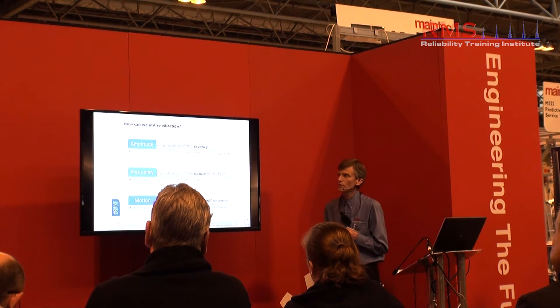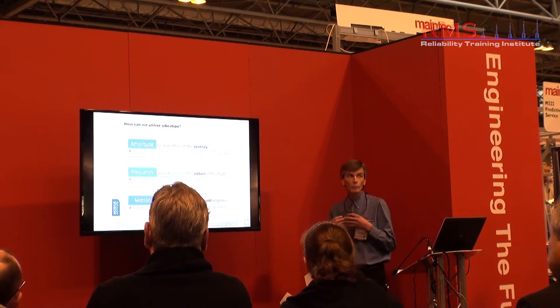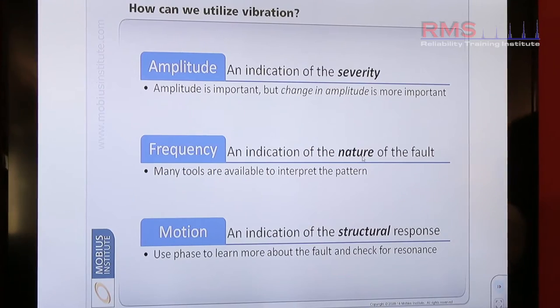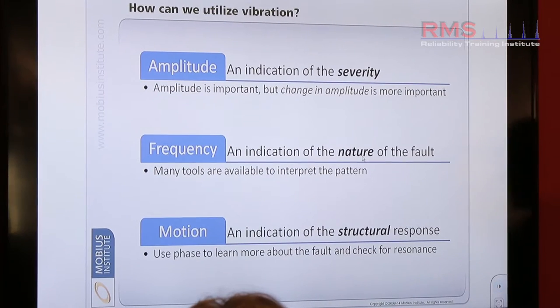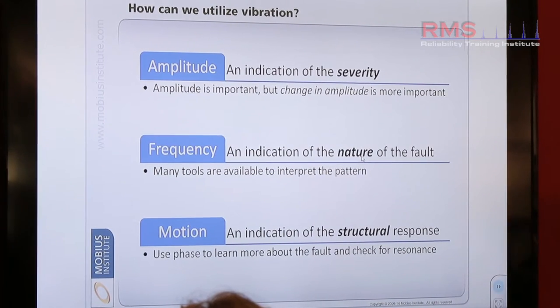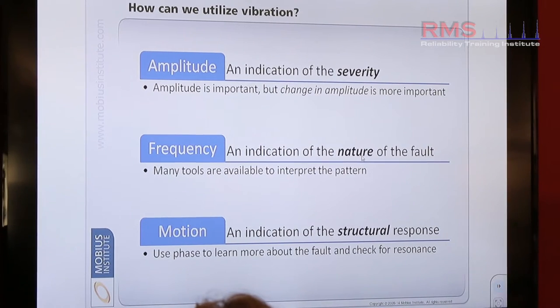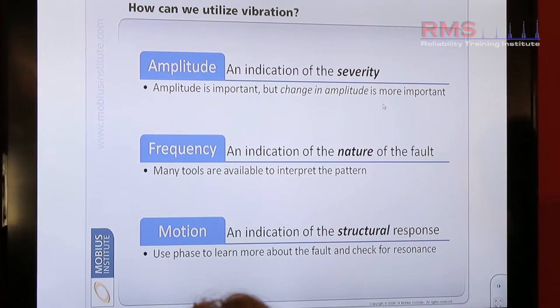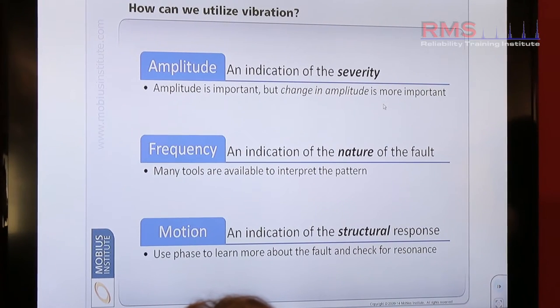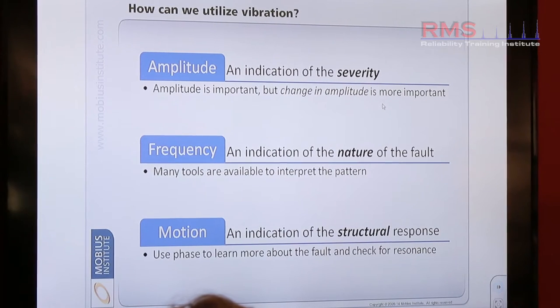Just a little bit of theoretical stuff here before we move forward with some signals and understand how these heartbeats produce themselves. One of the key aspects of vibration condition monitoring is we're trending and tracking the health. Most importantly, we measure the amplitude — how small the vibration is, or how large it might be because our machine has a problem. The amplitude is important, but the change in amplitude is important as well. Condition monitoring is about looking for change — trend and track the health and look for change.